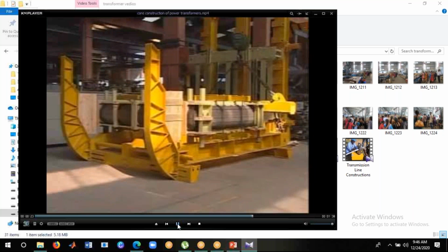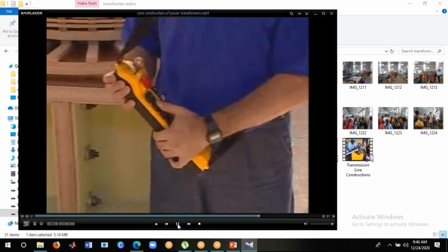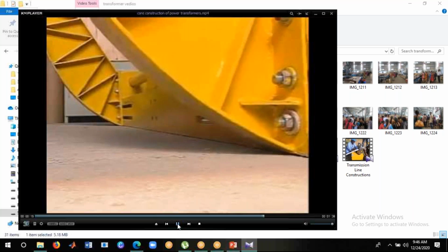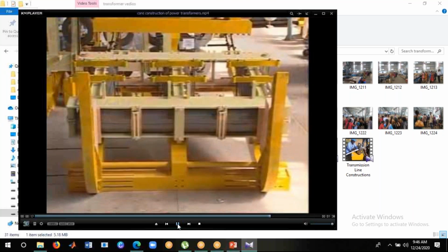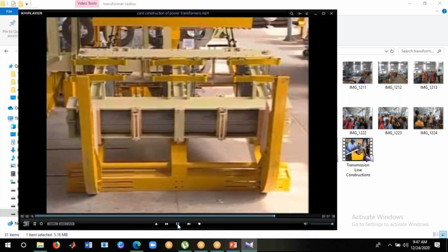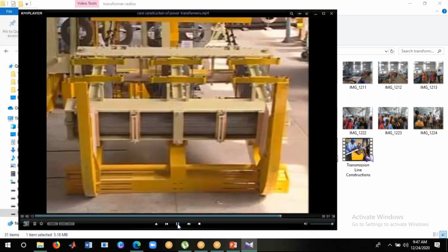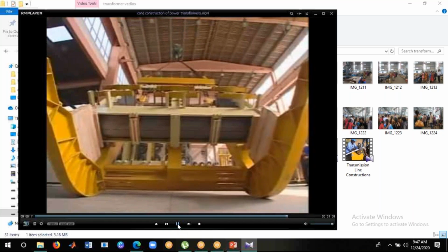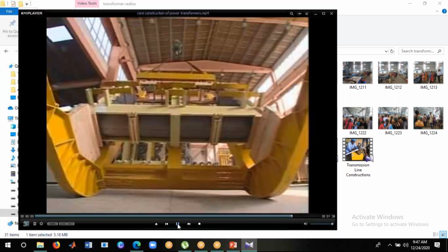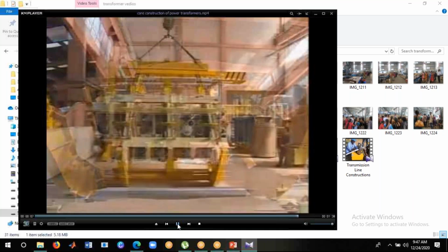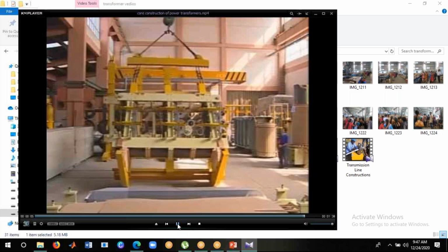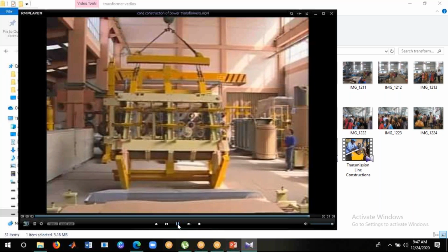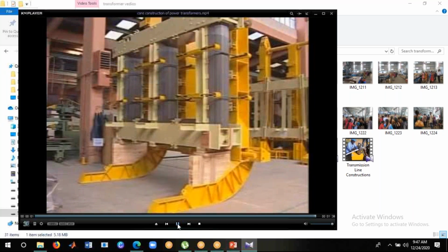Special stacking table is erected with a crane. The core is prepared for assembly. Upper yoke is placed after the coils are fit and compressed with yoke plates. With glass fiber reinforcement bands, homogeneous press force is obtained.